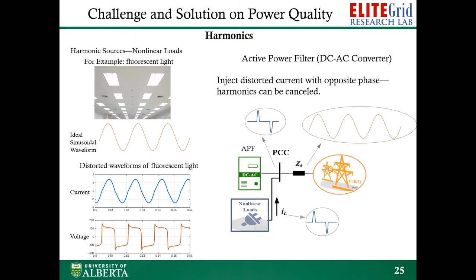The waveform in our grid is expected to be sinusoidal, like the waveform here, but the light will cause the current to be distorted, like some distortion can be found in this sinusoidal-like waveform. To cancel these harmonics, we can use an active power filter, which is a power electronics converter, to inject distorted current with opposite phase, so we actually cancel these harmonics and make sure the grid current is sinusoidal.